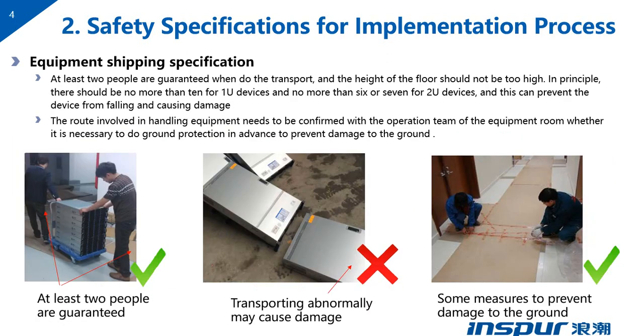Equipment shipping specification. At least 2 people are guaranteed when doing the transport, and the height of the floor should not be too high. In principle, there should be no more than 10 for 1U devices, and no more than 6 or 7 for 2U devices, and this can prevent the device from falling and causing damage. The route involved in handling equipment needs to be confirmed with the operation team of the equipment room, whether it's necessary to do ground protection in advance to prevent damage to the ground.